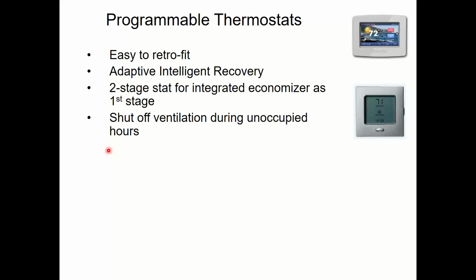So what we need is an extra output on the thermostat, one that's not there now, that says, hey, economizer, you should be in the occupied or the unoccupied mode. So one extra wire goes from the thermostat up to the rooftop's ventilation input on the economizer and tells it it's daytime or nighttime, or occupied versus unoccupied time. And if it's unoccupied, we shut the damper. Because I don't want to bring any ventilation air in for a building that doesn't have any people. There's no point in doing that. We talked about that last week. You only have to ventilate if people are there.